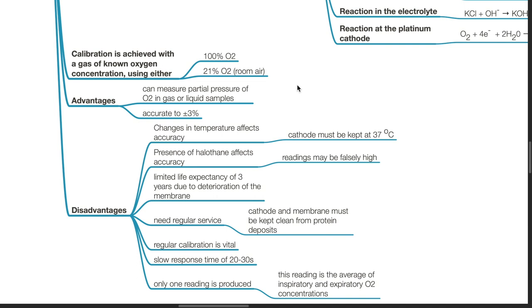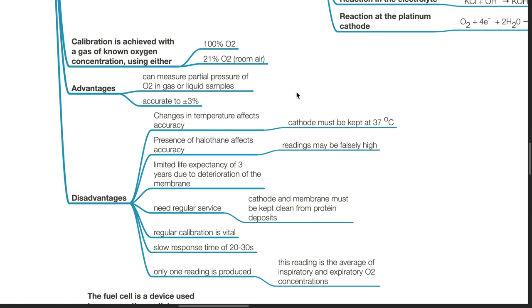Advantages of the Clark electrode: it can measure partial pressures of oxygen in gas or liquid samples, and it is accurate to ±3%. Disadvantages: changes in temperature affect its accuracy, and the cathode must be kept at 37 degrees Celsius. Presence of halothane affects its accuracy and readings may be falsely high. It has a limited life expectancy of 3 years due to deterioration of the membrane, and it needs regular servicing. The cathode and membrane must be kept clean from protein deposits, and regular calibration is vital. It has a slow response time of 20 to 30 seconds, and only one reading is produced, which is the average of the inspiratory and expiratory oxygen concentrations.